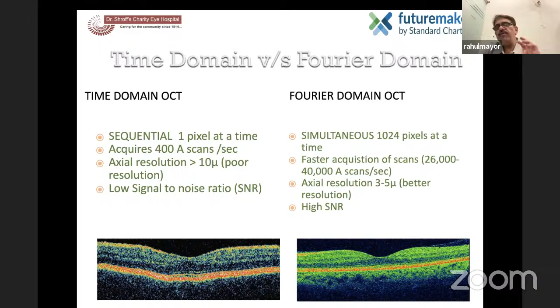The newer ones being the swept source and the spectral domain OCTs. The swept source obtains time encoded information by sweeping a narrow bandwidth laser through the broad spectrum, and it detects the backscattered intensity with a photodetector, not a spectrometer, whereas the SDOCT uses a charge coupled device camera for intercepting. Grossly, the resolution is the same for both, whereas the image depth is more for a swept source OCT than the SDOCT.